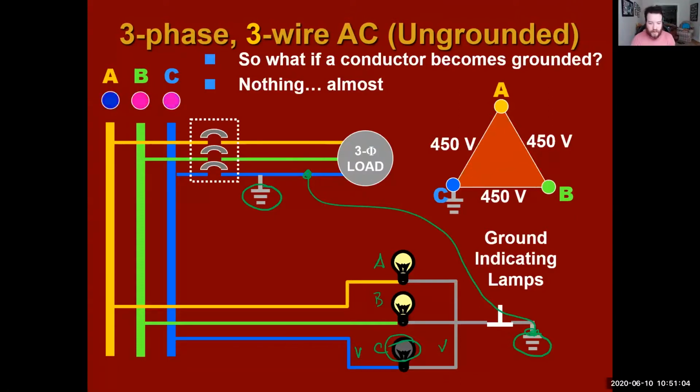But what's going to happen over on B and A, and this is where it gets interesting, is that now instead of having a ground voltage of 0 on this side, you have a voltage of C. So the power of C is going through the ground and, like I said, attaching itself to the opposite side. So now you have a greater potential difference than from B to 0.